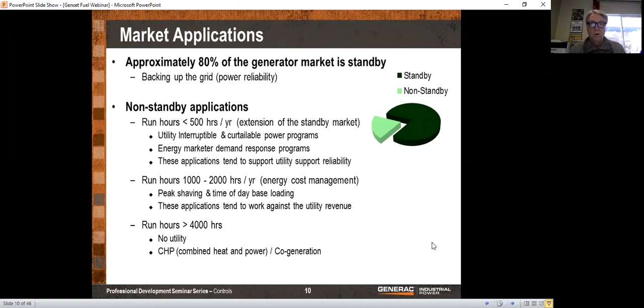Some run less than 500 hours a year - those are utility interruptible and curtailable power programs. Those running 1,000 or more hours could be used for peak shaving, and anything more than 4,000 hours we generally consider a prime power, full-time application. We see a lot of those in combined heat and power, what used to be called cogen.